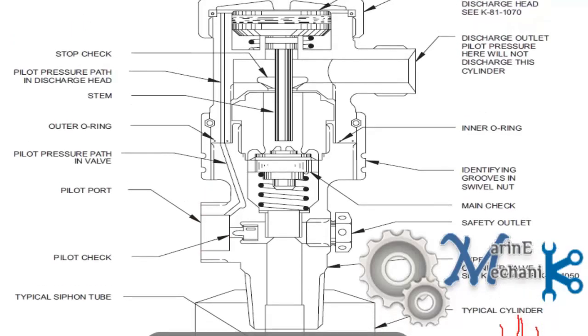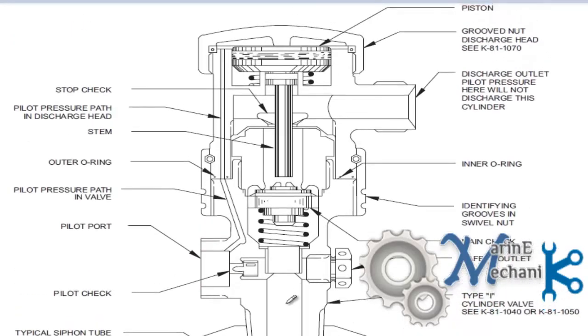So now, as you know, the bottle pressure, the CO2 comes here along with the spring force, and keeps this valve closed. Now you're operating the CO2 pilot bottle. The CO2 comes here. This pilot check valve cannot be opened by the lower pressure CO2 from the pilot bottle. The 1 or 2 kg CO2 from the small pilot bottle cannot open this pilot check valve, because the CO2 inside the main bottle is at higher pressure, so the back pressure is more. So it will travel through this path. I'll change the color. Just trace out this blue line. It climbs up, goes here and activates this piston.